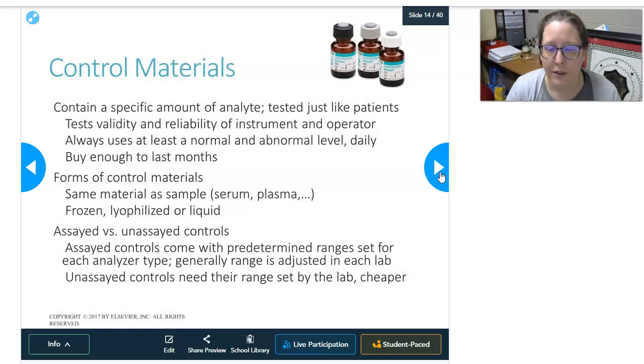And then there are assayed and unassayed controls, and that has to do with what you want to purchase. Assayed are always more expensive than unassayed. The difference between the two is this: assayed controls come with a predetermined range that's already set for each analyzer type and each analyte. So you already have a target. You can look up, they can give you the data to say, for your type of analyzer, for this analyte, level 1 should be in this range, level 2 should be in this range, level 3 should be in this range. And so you already have a target to aim at, and then you can adjust that range slightly for your lab, as each analyzer is slightly different.